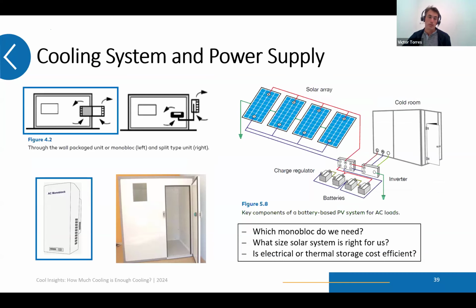The most typically used cooling systems are the ones described here in this figure. On the left, you have monoblock cooling units, a cooling system that is integrated in the sandwich panel. You just have a hole in the sandwich panels and you install the cooling system there. They are called monoblocks. Then there are the other systems that are a split type. It means you have the condensing unit outside and the evaporator inside.